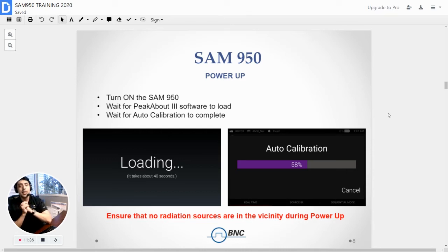It's using the internal potassium chloride source inside the device. This source is just like a banana, in the amount of potassium it has. With the source, the system will calibrate the spectrum using the 1460 peak. So it's calibrating to adjust to a change in temperature, change in altitude. If it hasn't been used that frequently, it'll adjust to the various settings.